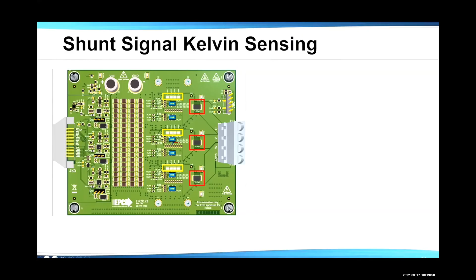Here's how we do the sensing: we make a Faraday cage of analog ground on top of one layer, with the signal connecting to the leg also surrounded by analog ground. On the other layer we close the Faraday cage with analog ground to protect this low impedance source signal.